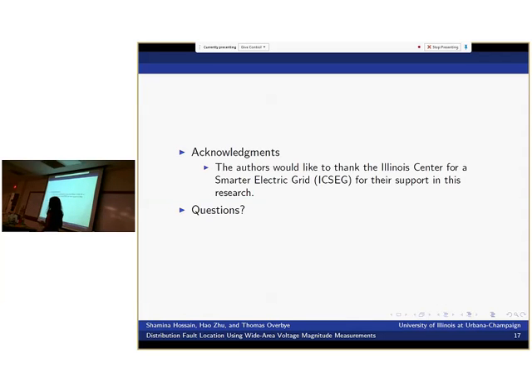So can you say what's the difference of your work to other fault location algorithms in the literature? Well, of course there is present work that uses voltage sag data, as I did, looking at the pre-fault and post-fault voltage. But all of those still use the current data to either update their load models so they can compare those voltages, or, I think another one was using a pattern recognition technique. All of them still depend on that current value, sometimes pretty heavily. So a big difference between mine and theirs is I am mostly just concerned with the voltage magnitude, and I'm not even looking at the current.